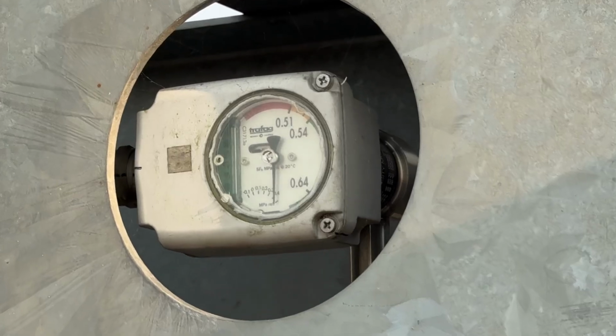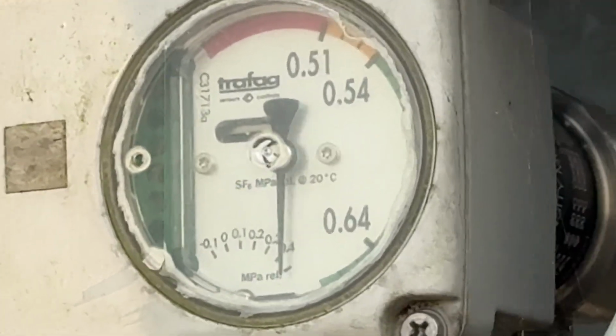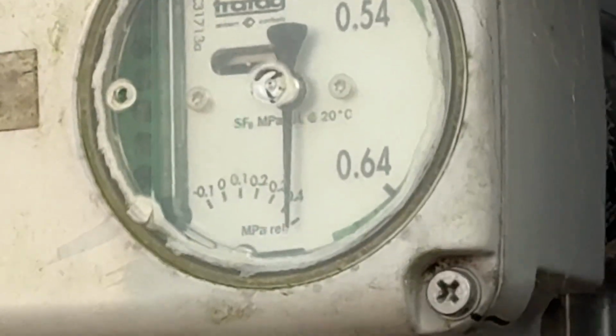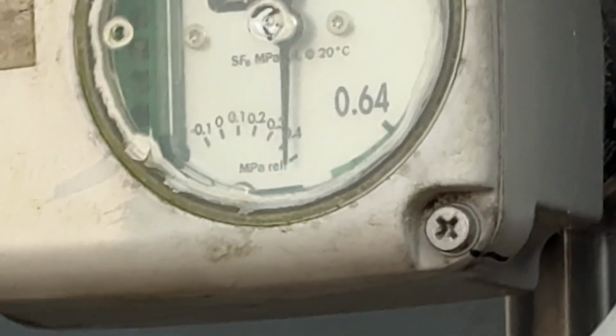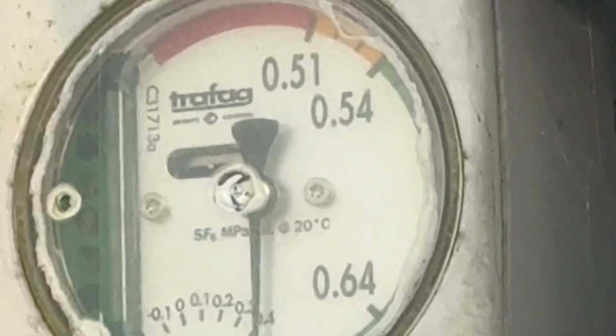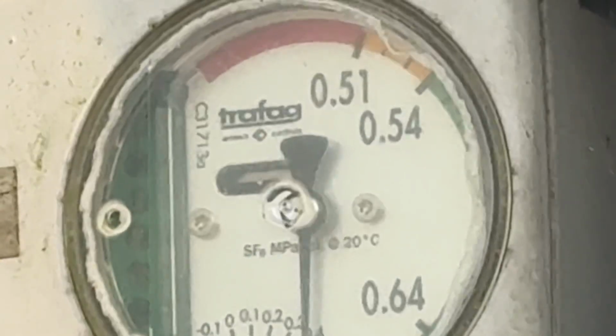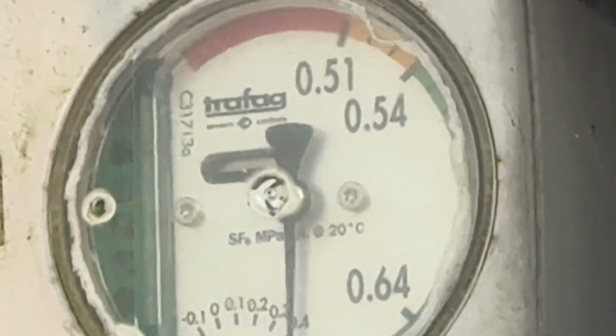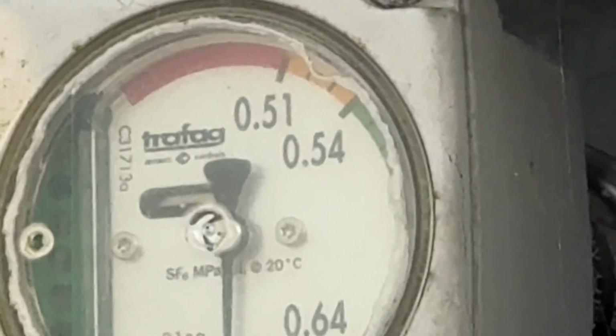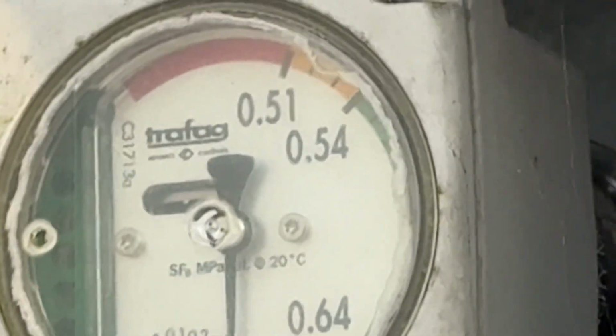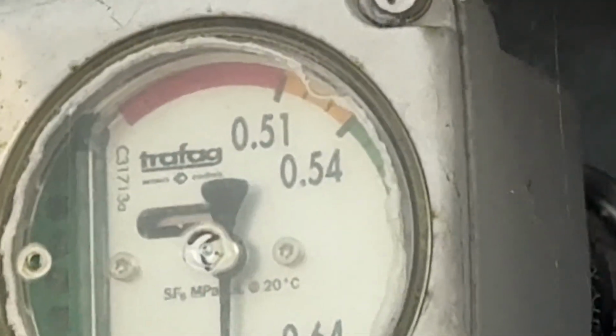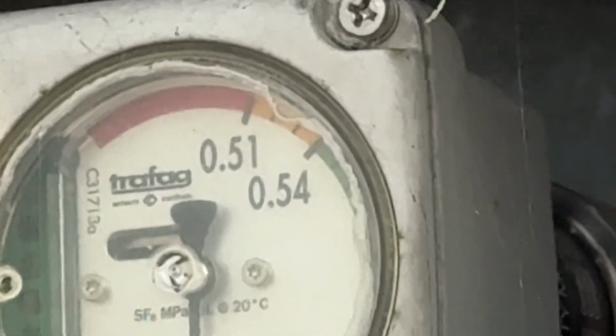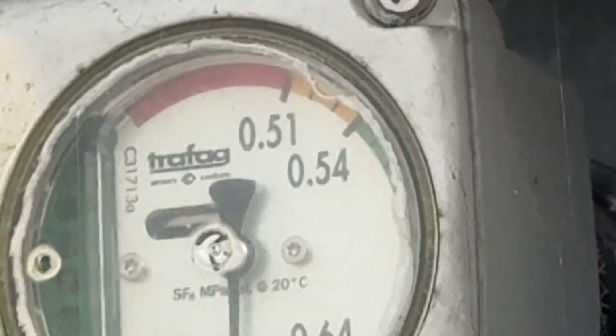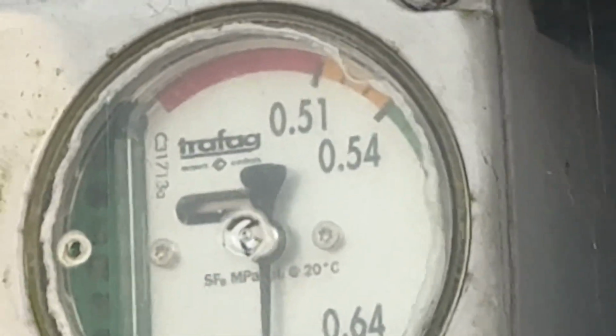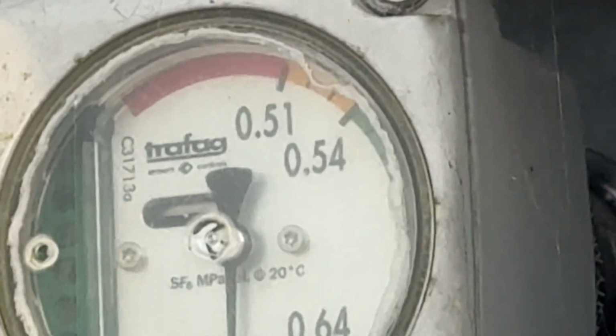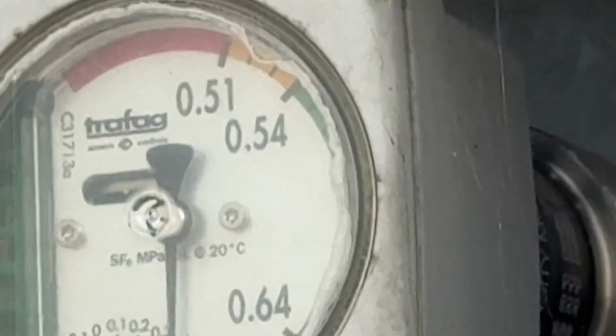This one is the SF6 gas density meter. Below 0.51 it is the red zone. In this zone it is strictly prohibited to operate the circuit breaker, on load or no load, under any condition. 0.51 to 0.54 is the alarm condition, showing that we have to check the gas pressure and fill again, because it is the stage before the danger condition.